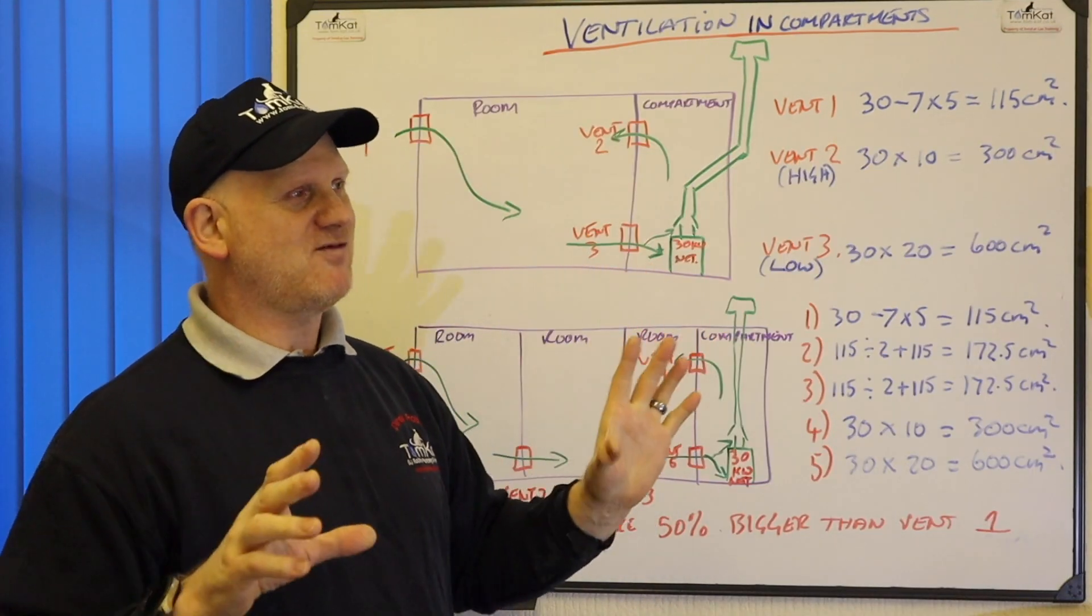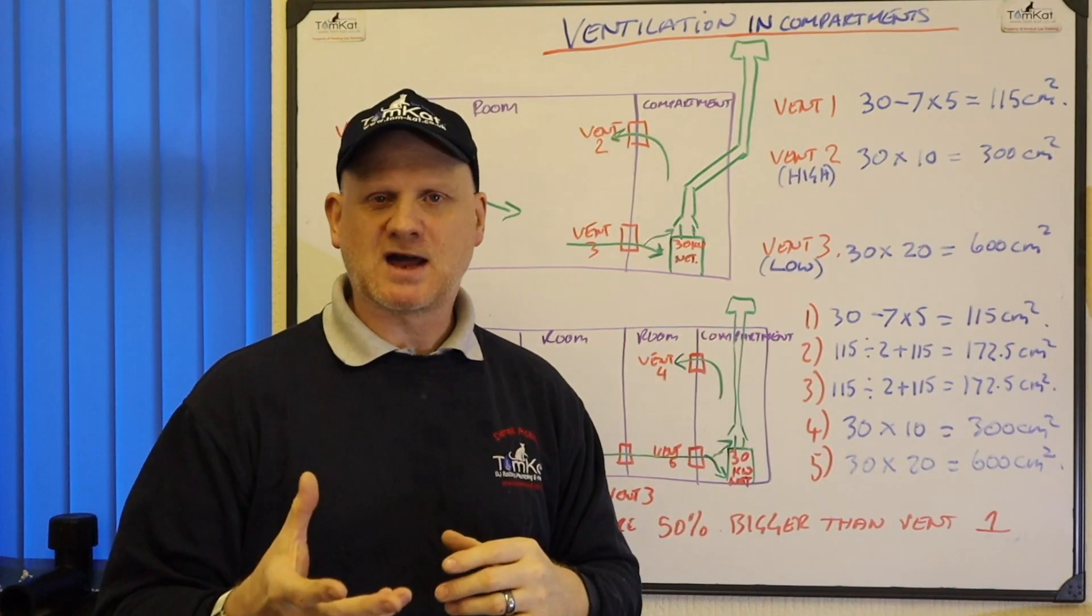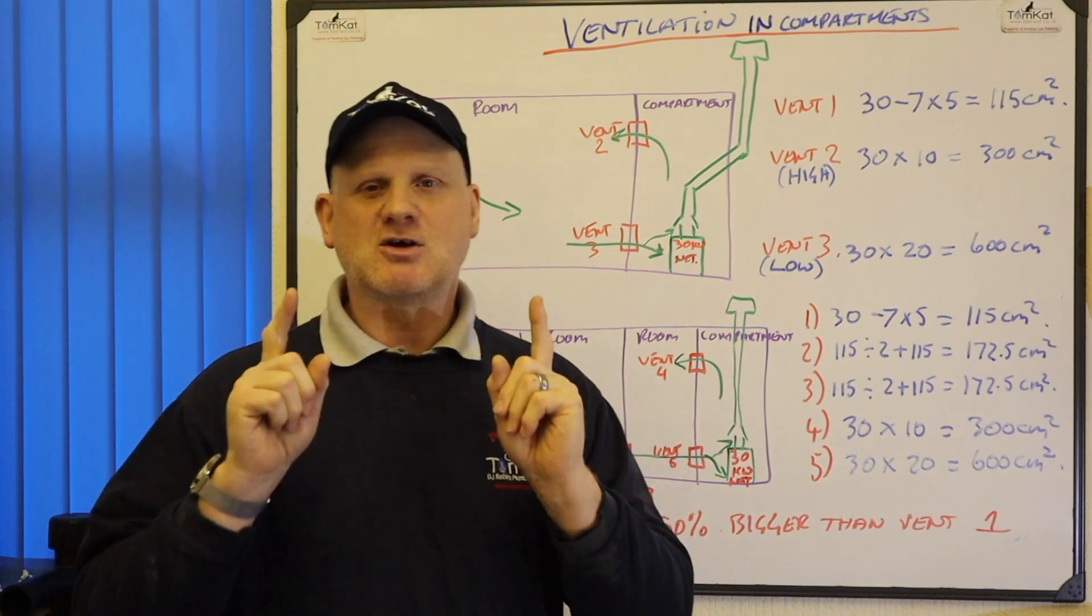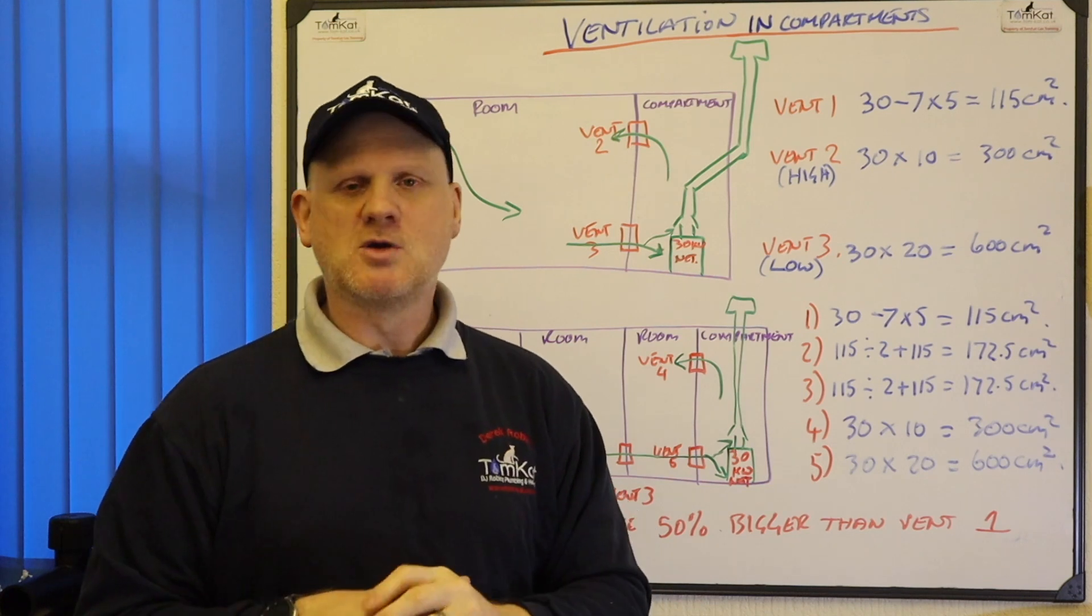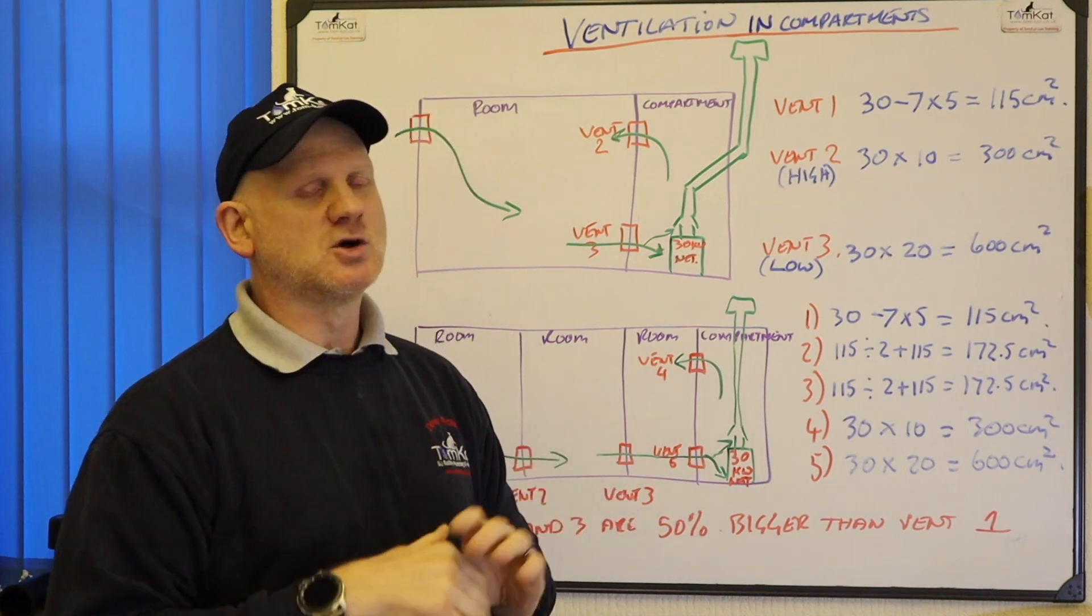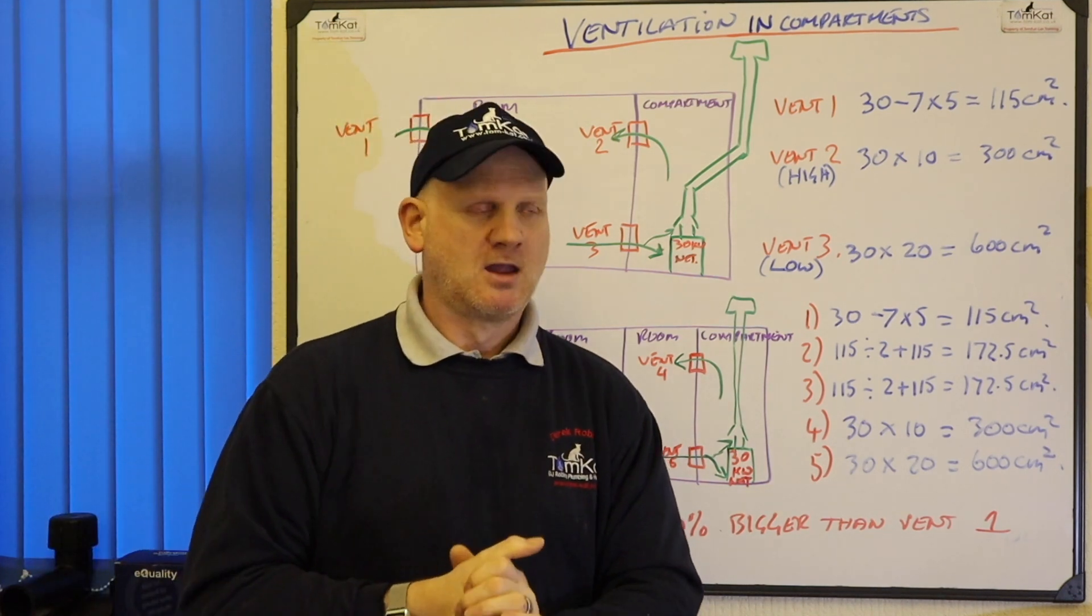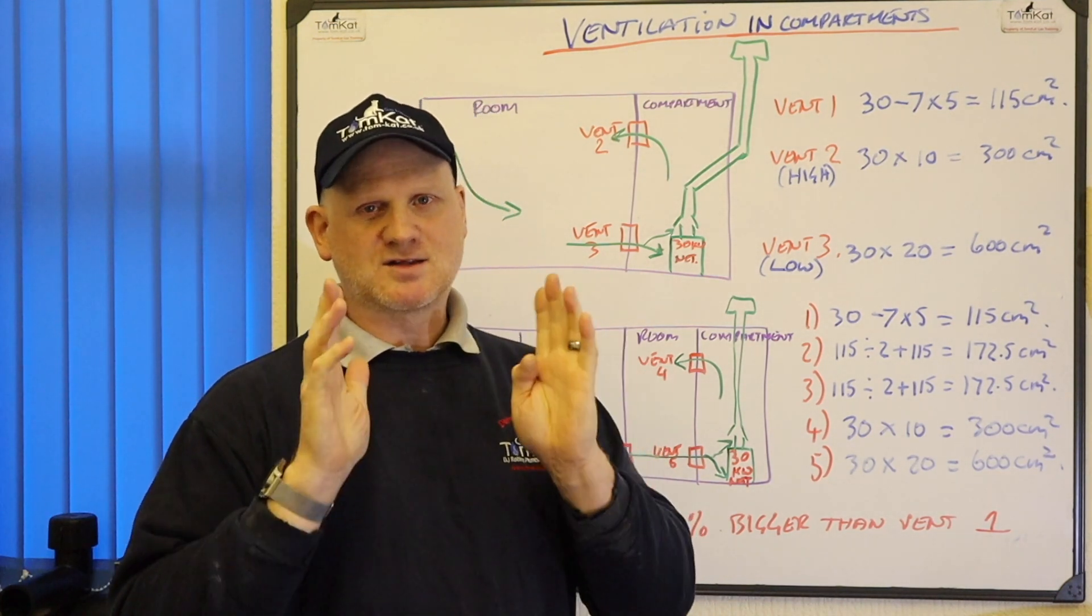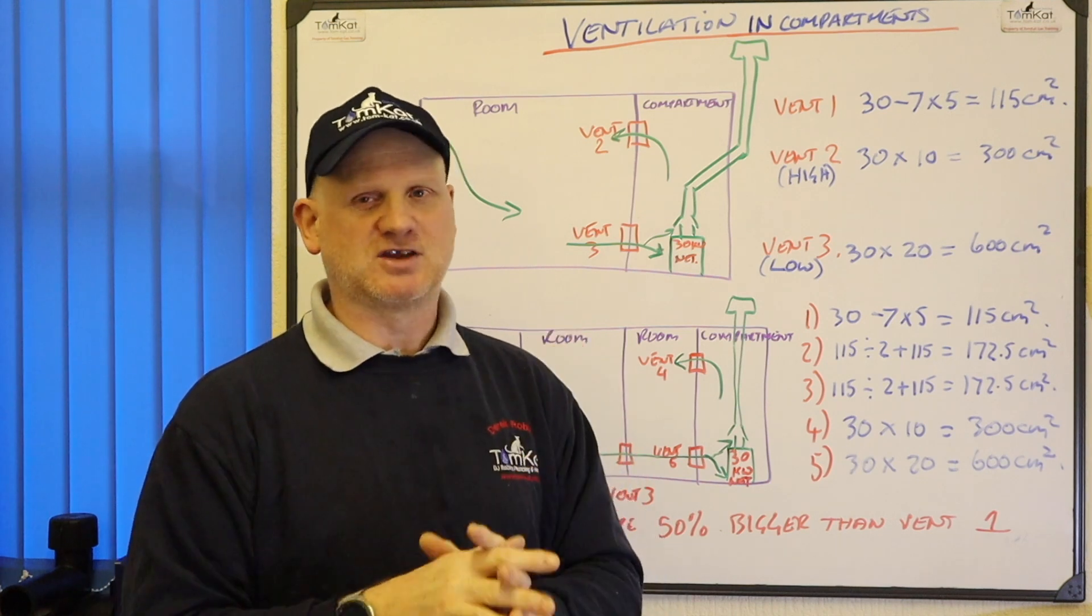Now a couple of things different to open flue appliances being installed in rooms to being installed in a compartment. As you've seen in the first one, if it's installed in a room we are allowed to deduct advantageous air. When the boiler is installed in a compartment you don't minus the advantageous air or the 7kW.